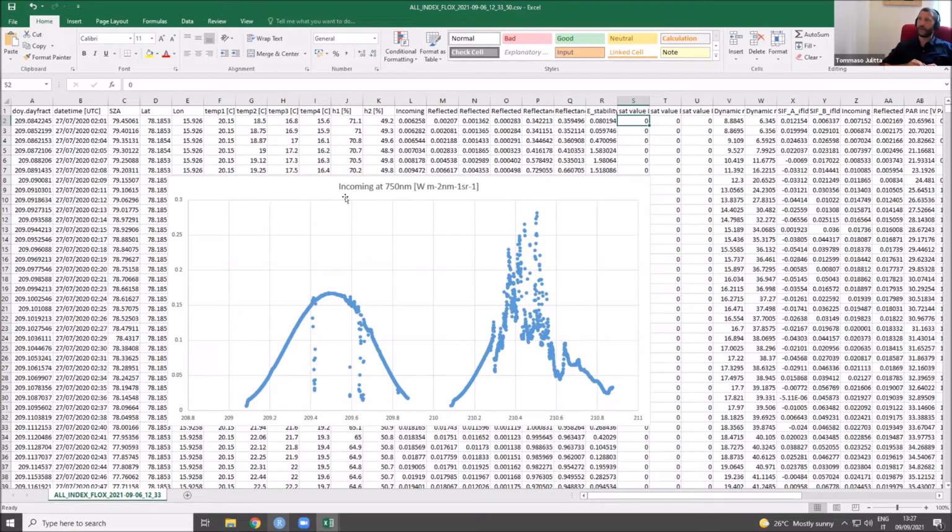Let's say that the maximum time to get the measurement in this case is 12 seconds, but then you need to consider that you also need to collect the dark current of the other channel. So in total, I would say it is 4 times 5, 20 seconds, plus maybe 5-6 seconds of optimization, the maximum. So that means you are getting reliable measurements every 30 seconds? Yeah, 30 seconds could be a good approximation. First one spectrometer is operating, then the other.